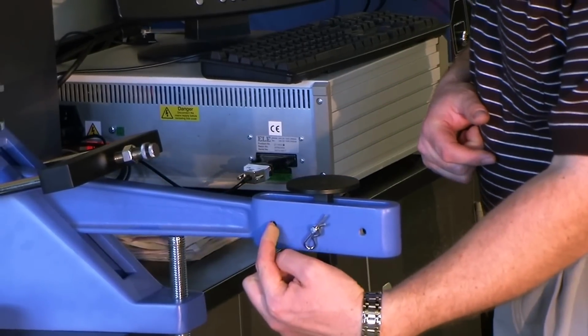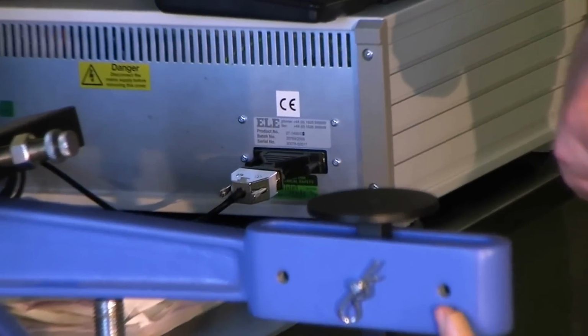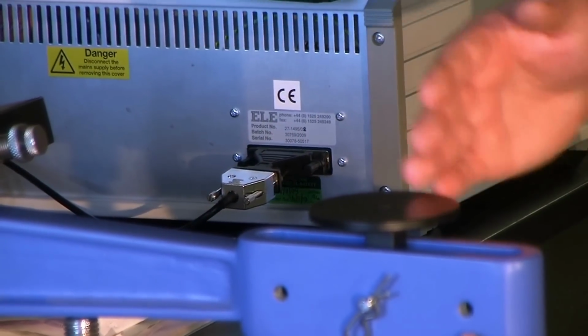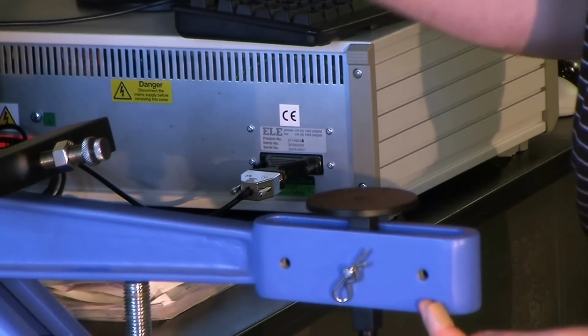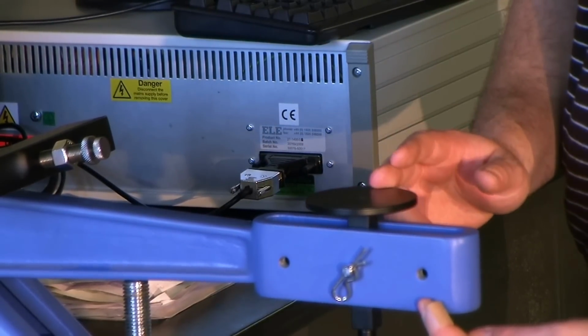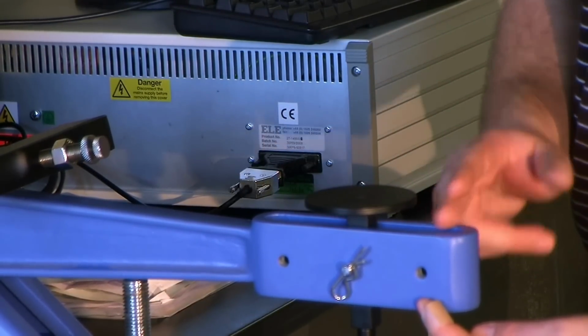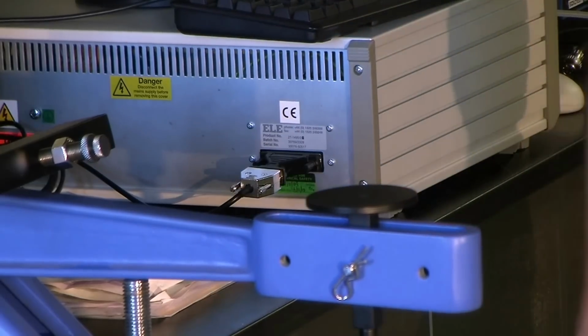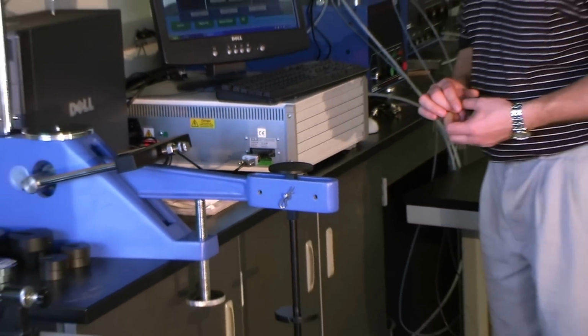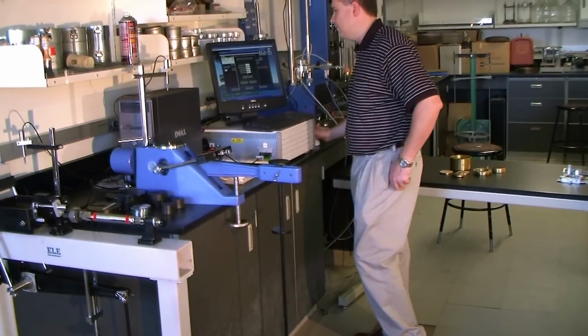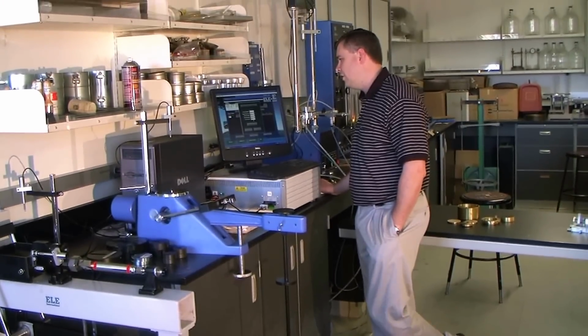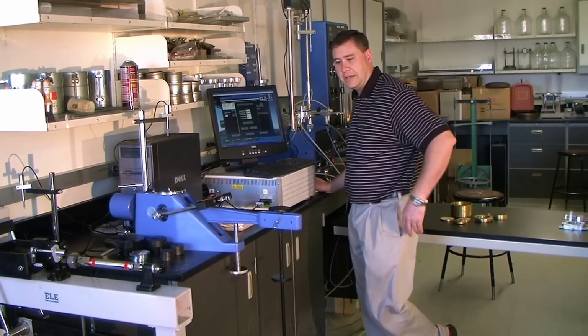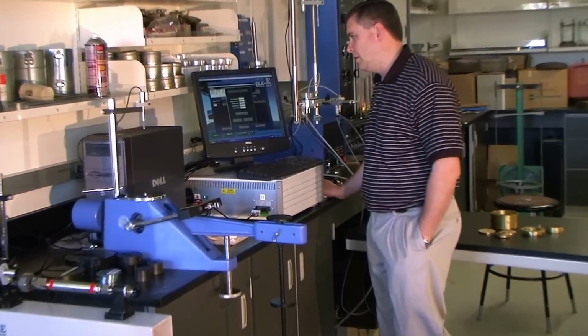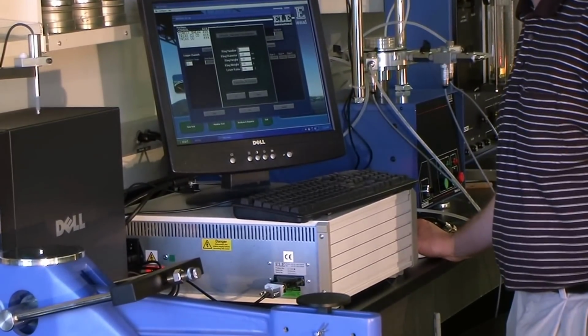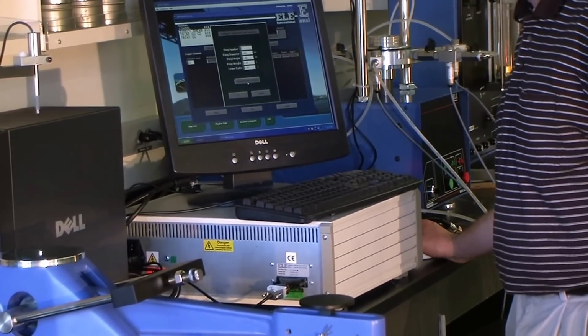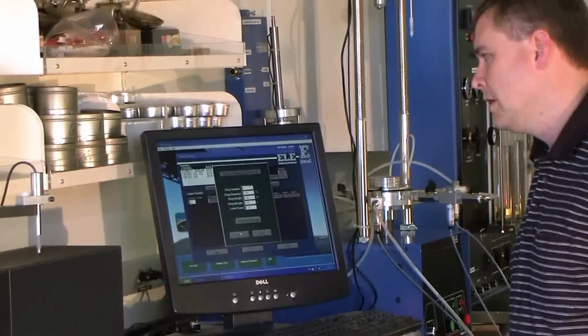These are a 9-to-1, 10-to-1, and 11-to-1 ratio for your weight application. You can calculate the amount of stress that's on that depending on which ratio and how much weight you apply, obviously taking into consideration the diameter of your sample, the surface area of your sample. So you can put that on here as default, or you can leave them blank and fill them in as you go along if you do change those. You also have the frame correction for this type of machine as well.